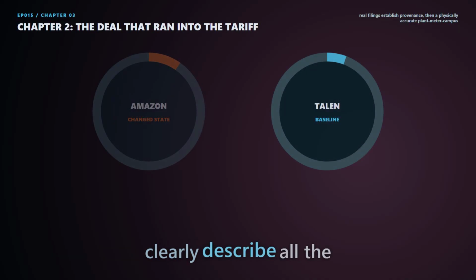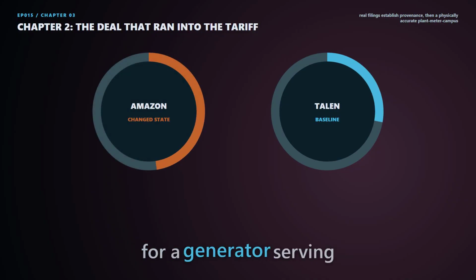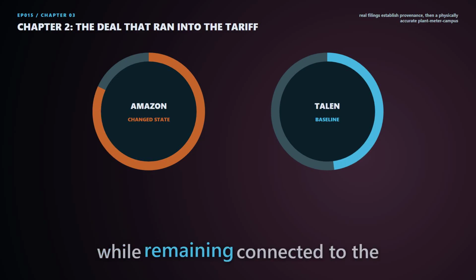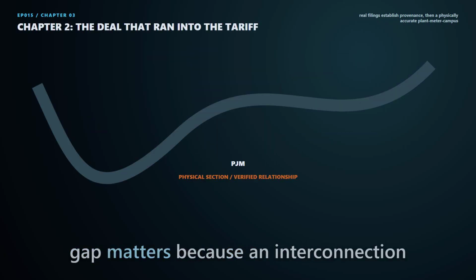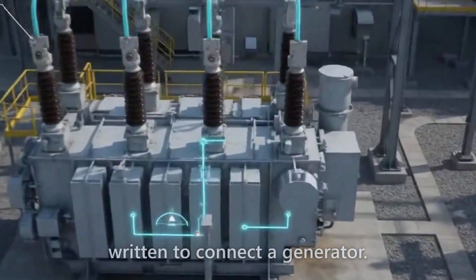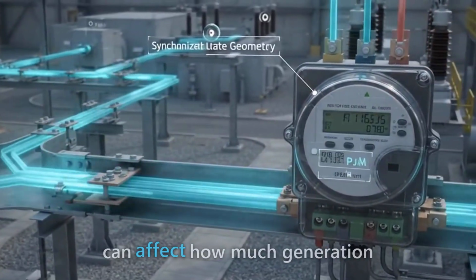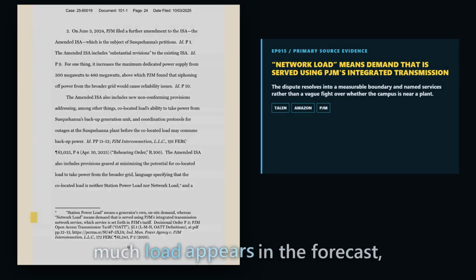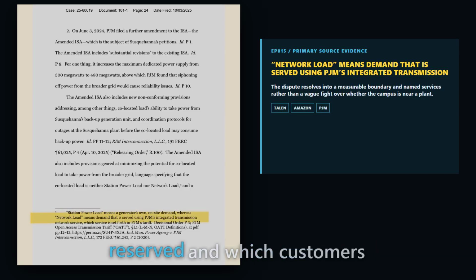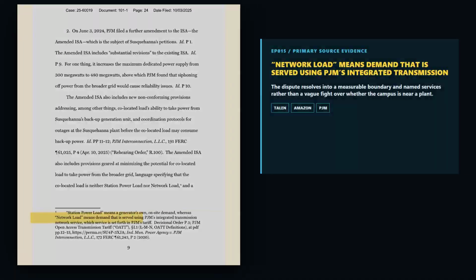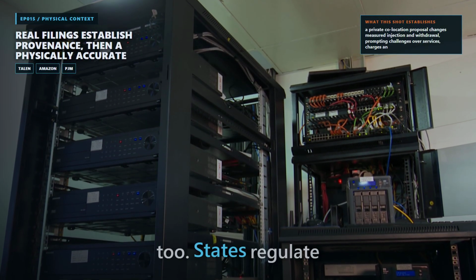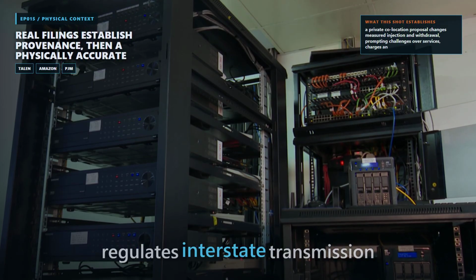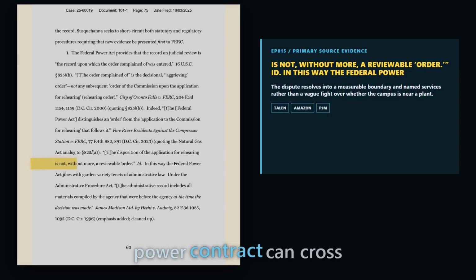PJM's tariff did not clearly describe all the rates, terms, and conditions for a generator serving a large co-located load while remaining connected to the regional system. That gap matters because an interconnection agreement was originally written to connect a generator. Expanding it to govern a huge new customer can change more than a wire. It can affect how much generation PJM counts, how much load appears in the forecast, what transmission service is reserved, and which customers pay for shared system functions. The parties argued over jurisdiction too. States regulate retail delivery. FERC regulates interstate transmission and wholesale power. PJM administers a regional tariff. A private power contract can cross all three without fitting neatly inside any one document.